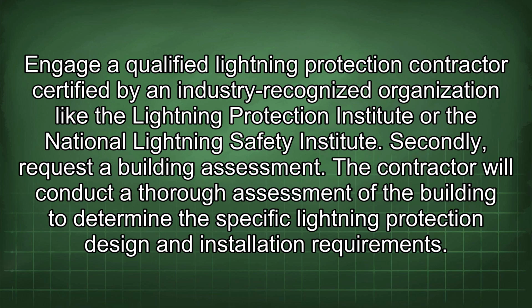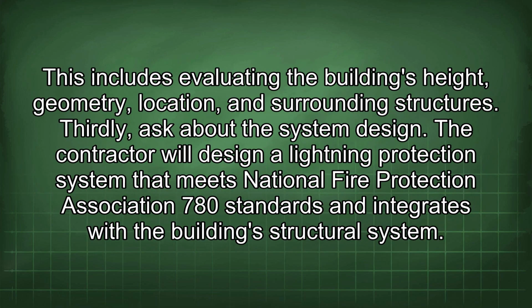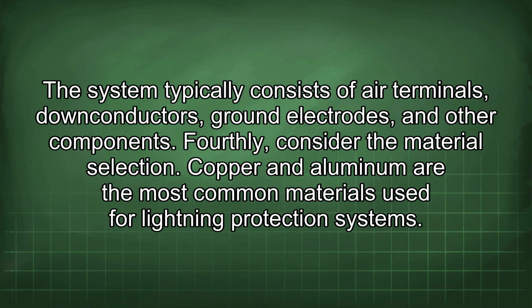The contractor will conduct a thorough assessment of the building to determine the specific lightning protection design and installation requirements. This includes evaluating the building's height, geometry, location, and surrounding structures. Thirdly, ask about the system design. The contractor will design a lightning protection system that meets National Fire Protection Association 780 standards and integrates with the building's structural system. The system typically consists of air terminals, down conductors, ground electrodes, and other components.